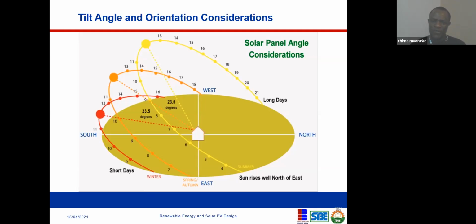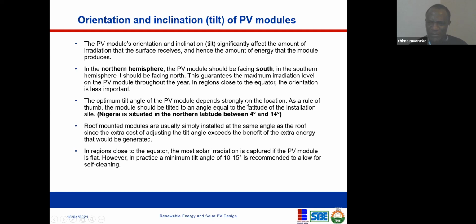If you're in the south, like Bayelsa River, the latitude is about 4 or 5, but as you move towards the north, the latitude increases to about 12 or 14. So if you're installing a solar PV in Nigeria, here's a rule of thumb: the module should be tilted to an angle equal to the latitude of the installation site. Nigeria is situated in the northern latitude between 4 degrees to 14 degrees. So if you're installing a solar PV in Nigeria and you're tilting above 20 degrees, I don't understand what you're doing.